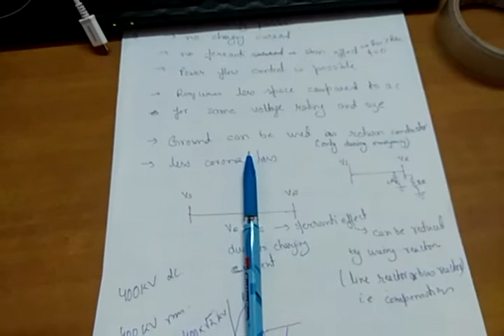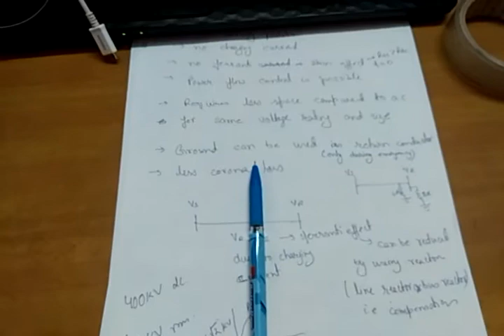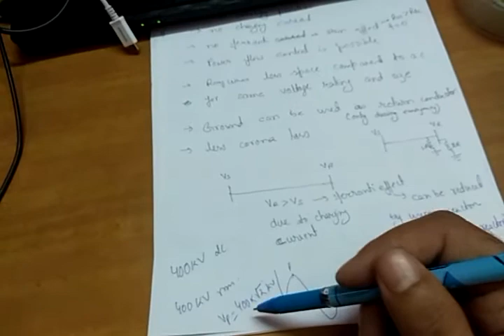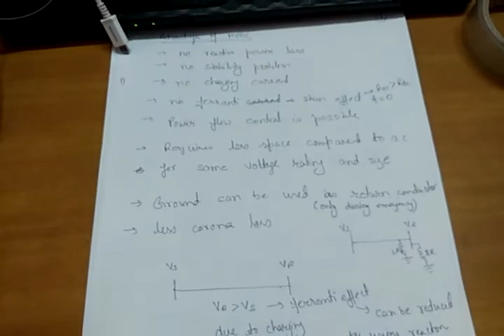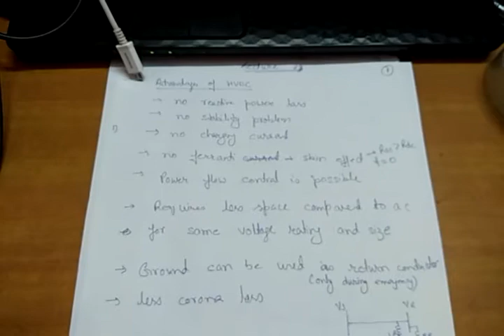So if we are designing a tower or insulator or anything, what will happen? The length of the cross arms will increase. The height of the tower will increase, because we are not designing it for 400 kV, we are designing it for 400 multiplied by root 2, that is the peak value. So this increases the cost. We need more space. That is why it is written that it requires less space compared to AC for the same voltage rating and size.